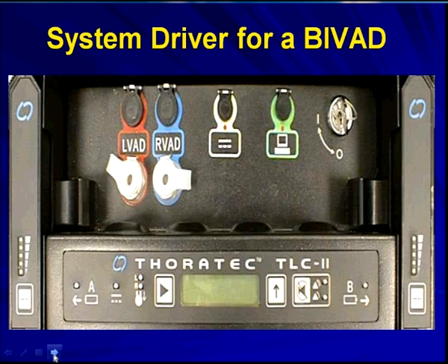And if you look where it says LVAD in the red and RVAD in the blue, there actually are hoses that connect to the LVAD and the RVAD. And next to those would be two little blue bulbs sitting on top of this system driver. Those blue bulbs would become the backup plan should this system driver completely fail. And those batteries that you see on the left and the far right were to completely die, and for some reason, this system driver completely shut off.